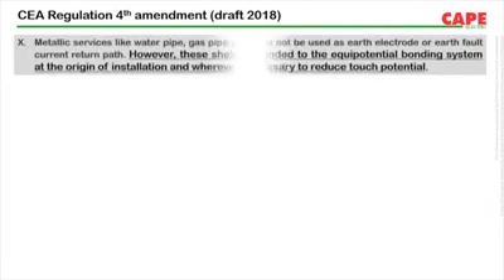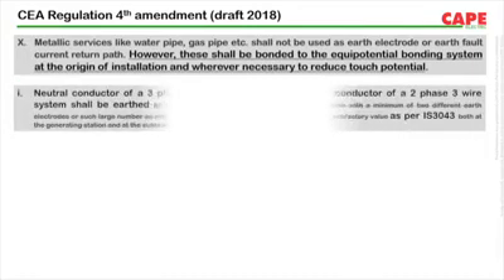In the CEA regulation 4th amendment draft, which was published at the end of 2018, in regulation 41, a number of changes have been made. For example, regulation 41X. You can read: however, these shall be bonded to the equipotential bonding system at the origin of installation and wherever necessary to reduce touch potential. With this change, the misinterpretation can be reduced to a large extent.